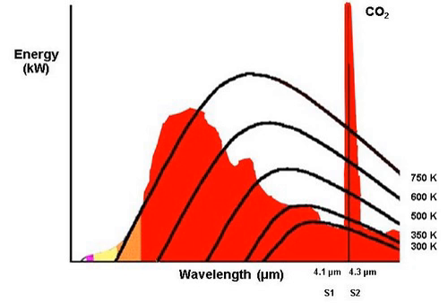Cone of vision. The cone of vision of a flame detector is determined by the shape and size of the window and the housing and the location of the sensor in the housing. For infrared sensors also the lamination of the sensor material plays a part, it limits the cone of vision of the flame detector. A wide cone of vision does not automatically mean that the flame detector is better.